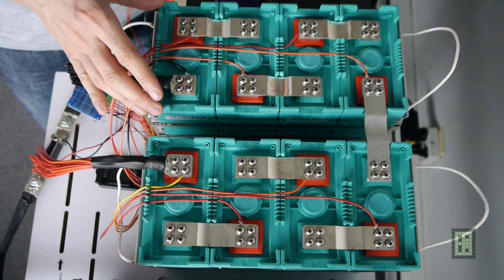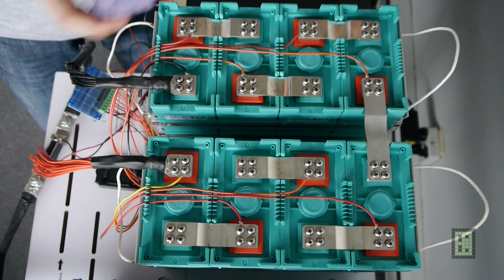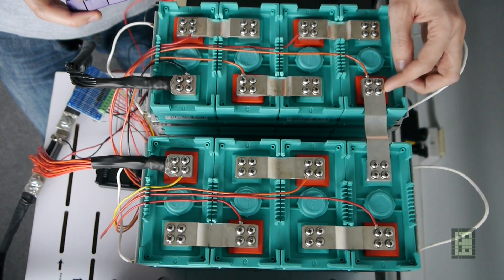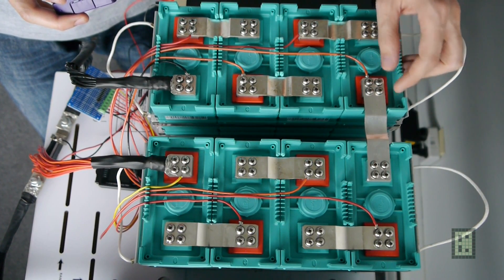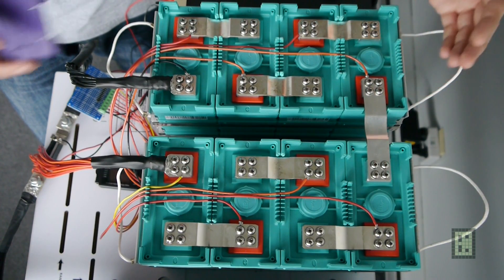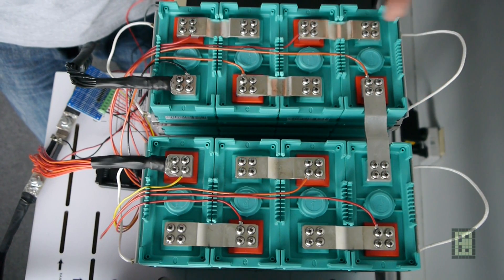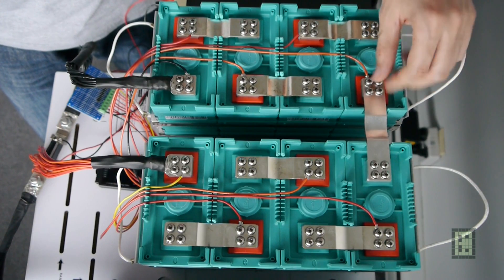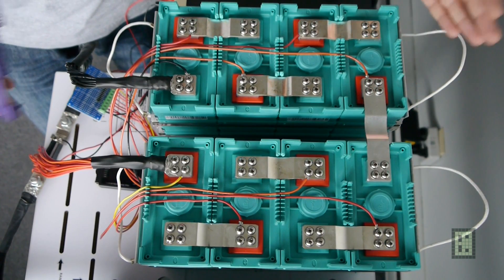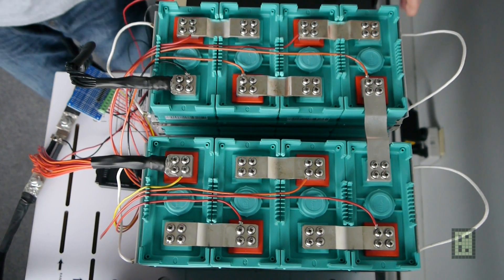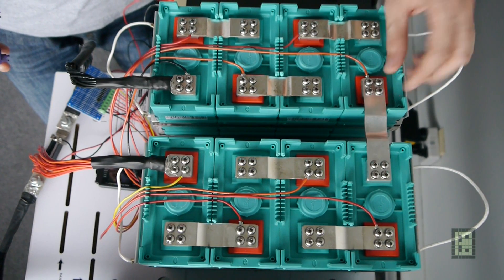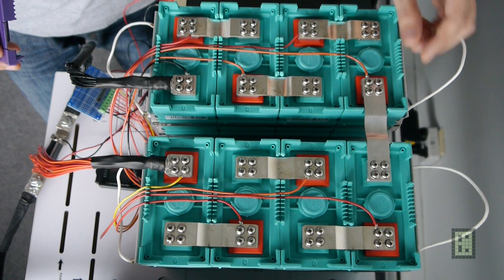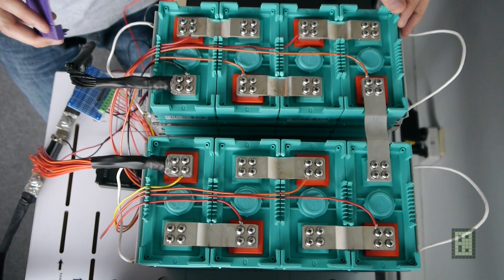These are the batteries. As you can see, I like this battery especially for the type of connector they use here. They are square and use four screws for each terminal, and I think these are a better solution than the other manufacturers that use round connectors on these large cells. You cannot damage the cell by screwing the nut too tight or something like that.